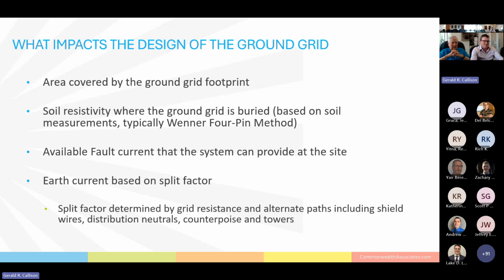So what is it that impacts the design of a ground grid? One of the significant factors is the surface area that the footprint is covering. The second significant factor is the soil that it's buried in. What is the resistivity of the soil? When we're designing a ground system, we'll create a soil model of different resistivities at different depths, based on measurements taken in the field, usually using the Wenner 4-pin method. So that's modeling soil, which is very important to the grid design.